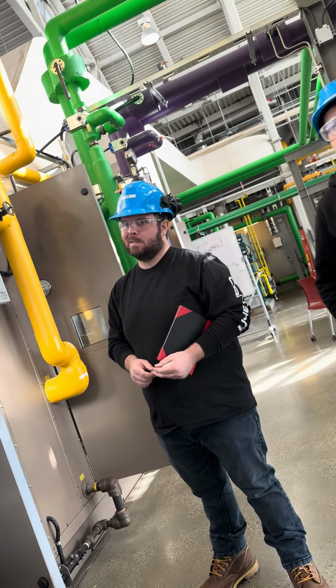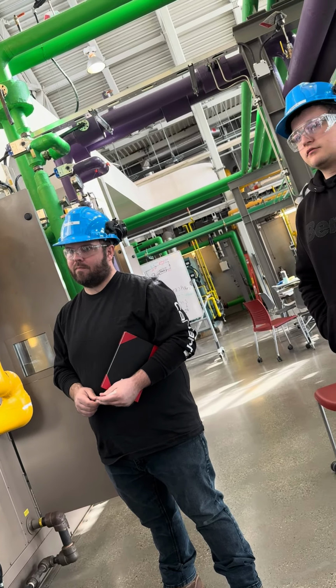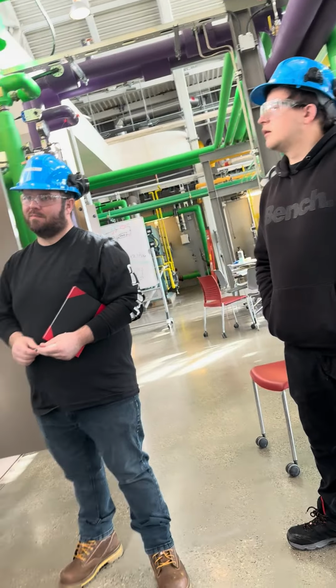So far we've brought in the outside air. It's minus 19 out there right now. We're going to hit our first set of coils. So if I have water in these coils and that cold air comes in, what's going to happen? It's going to freeze, right? So I may have to preheat that air. This is a mixture of glycol and water. So your first coil is always going to be glycol. We don't want it to freeze. And it's going to make sure that it gets to a minimum of 4 degrees.